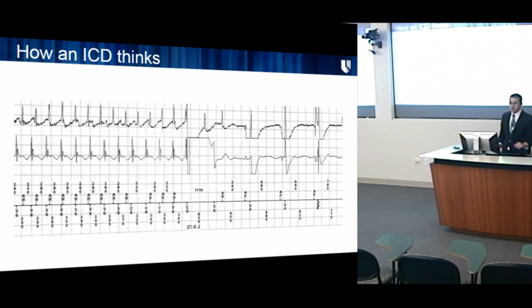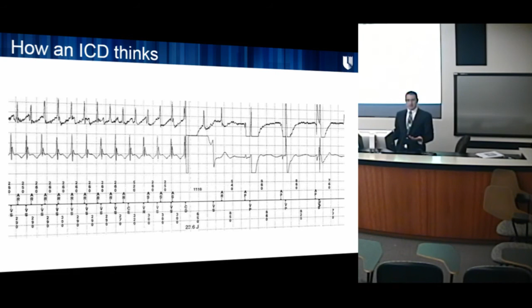So essentially what the defibrillator does is it takes all the information that we have given it in terms of programming, and it uses these algorithms to determine if what is going on is good or if it's bad. Because sometimes there's fast heart rates that maybe you don't want to shock somebody out of. So what if somebody's on a treadmill and their heart rate is like 180 beats per minute, and maybe that's okay. You don't want the defibrillator to shock the patient out of that, and so you want to make sure that the defibrillator knows what's what.